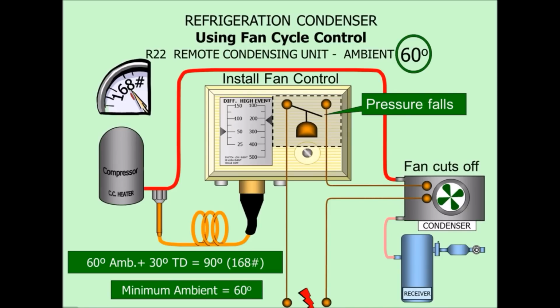So the first thing you'll have to do is install the fan control. Here it is right here. It does have a pressure sensing connection that you're going to connect to the high side of the system. You'll have to find a port to connect it to, and many times there'll be more than one high side pressure port on the condenser that you can connect it to. If not, you're going to have to install one, and that makes it just a little bit more difficult.